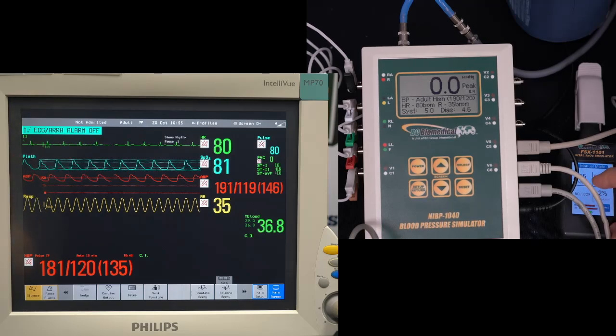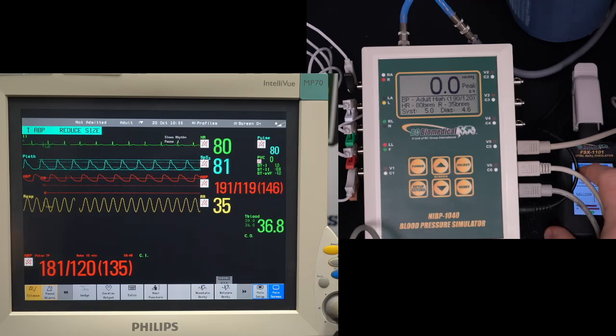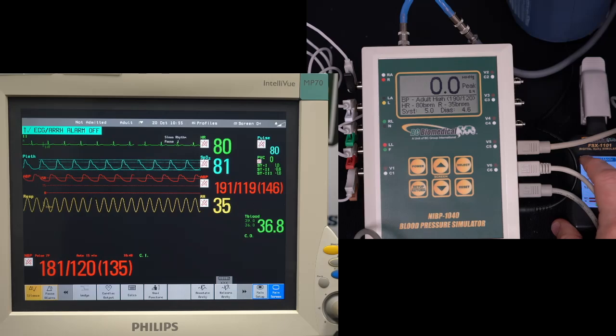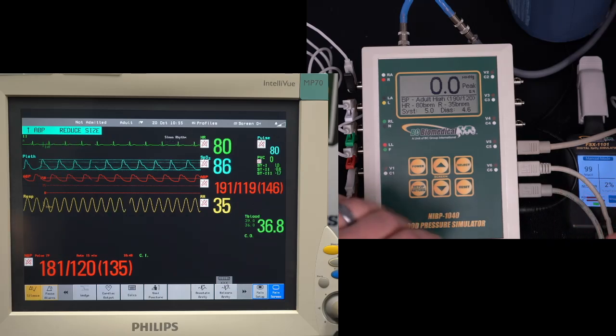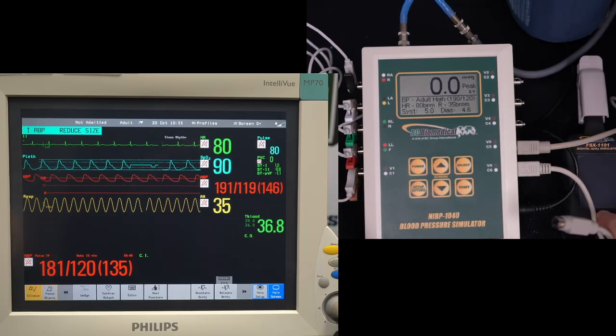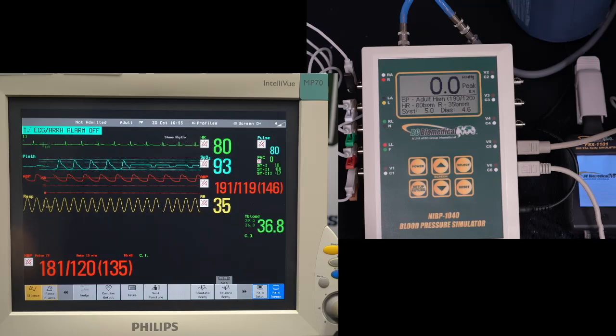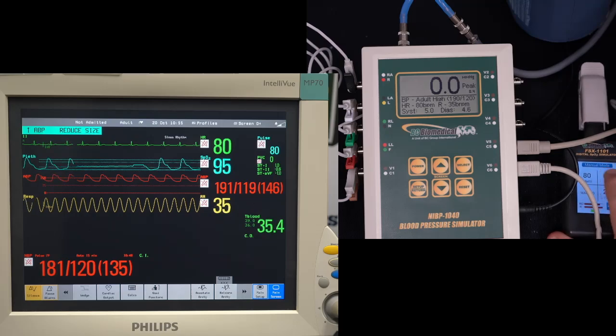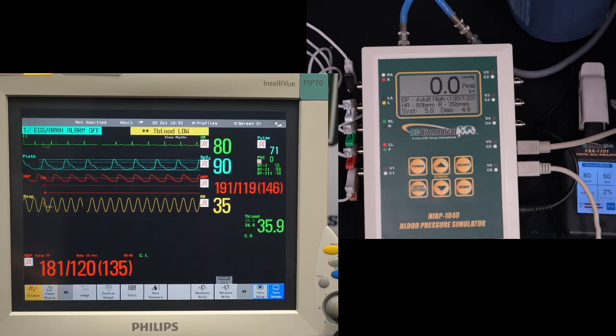If we want to change the SpO2 percentage, it's really easy to change on the FSX. We just click on the value that we want to change, and it'll cycle through those settings here. Also, if we don't have this synchronized, I'll disconnect this sync cable. That'll restart the SpO2. I'll show you that it's still possible to do these tests, but now we have an independent setting for the rate on the SpO2.